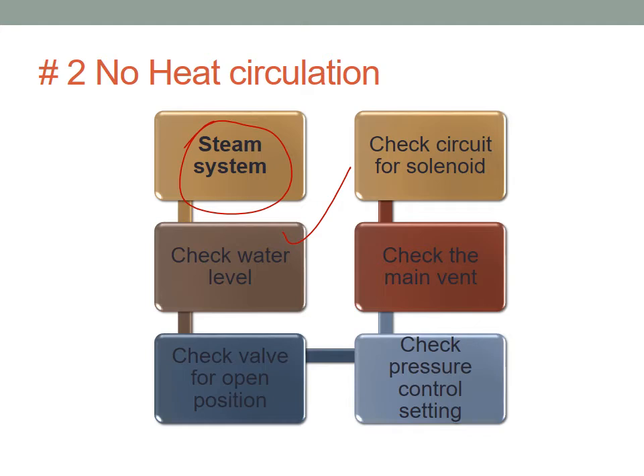And if we have an auto water feeder system, make sure it's functioning correctly because sometimes it doesn't. Check the valves are in open position. That could be a little bit tricky. Again, usually righty tighty, lefty loosey, so make sure it's all left. Check the pressure control setting, because if the setting is not done correctly, probably you are very low in pressure, less than 0.5, and it's not gonna turn on. Again, this could be electrical, not always.